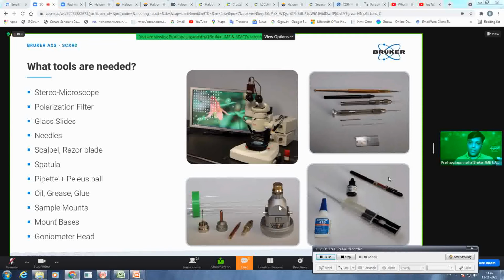So the goniometer head, which now comes with a magnetic base, which is ideal because you don't disturb your goniometer setup too much. So this will always be fixed onto your diffractometer. You just play with this crystal cap, just putting it onto the magnetic base here and then take it from there. Otherwise, previously what you were using was like this, and every time you are tightening this grub screw, after some time this grub screw loses its strength, and then you are collecting some data which has a lot of vibration or movement in the crystal, which is not good.